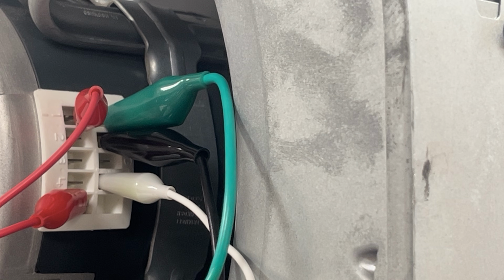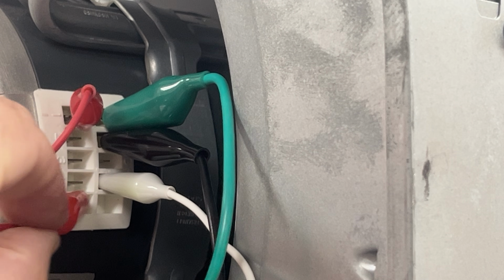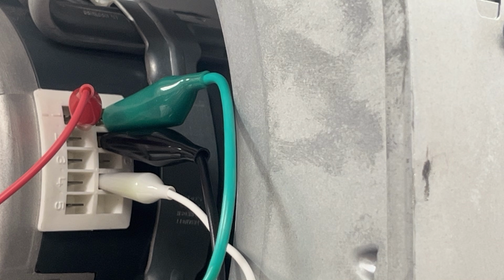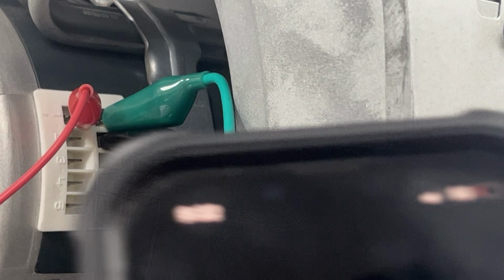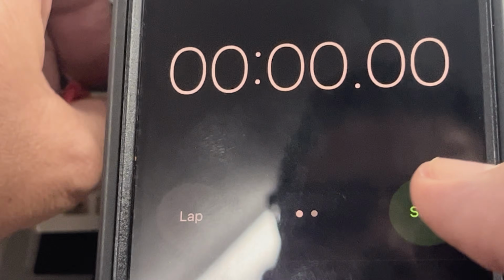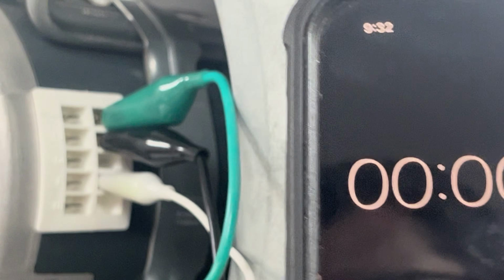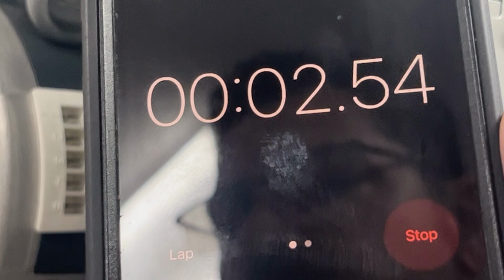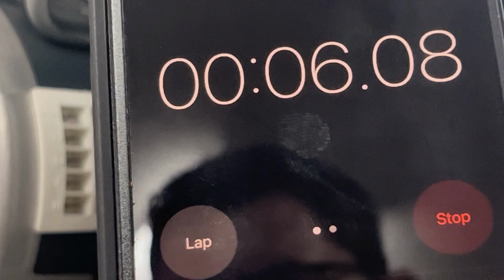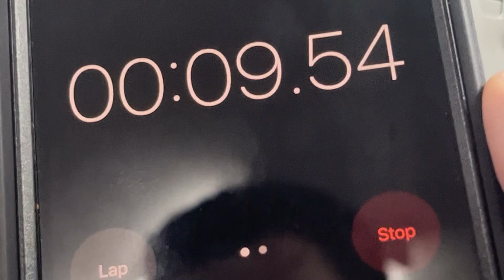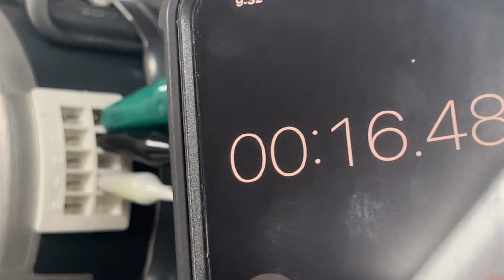Now I'm going to go ahead and remove power on number 5, and you'll see that the motor will rev itself back down. And I'm going to show you that off delay. The moment we go ahead and remove power from 1, it's a 90-second off delay. 90 seconds is a long time when you're waiting on it, so you got to be patient when you're doing this.